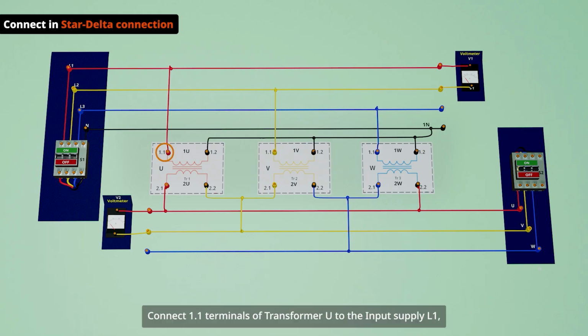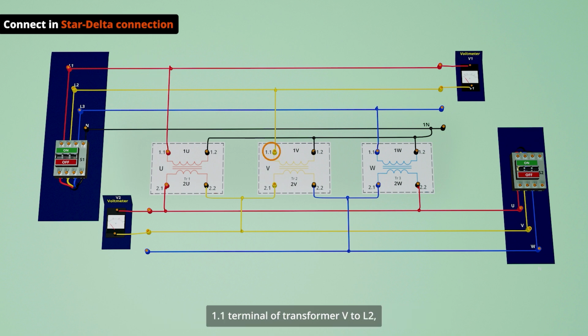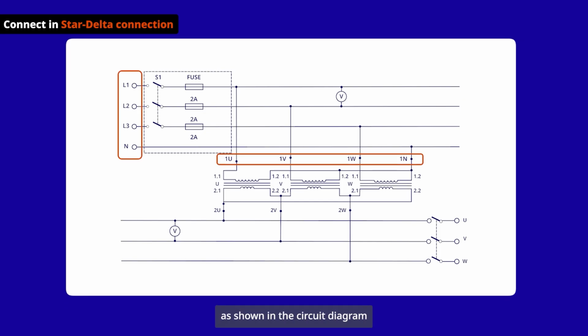Connect 1.1 terminals of transformer U to the input supply L1, 1.1 terminal of transformer V to L2 and 1.1 terminals of W to L3 as shown in the circuit diagram. Connect the dissimilar terminals of the secondary windings.